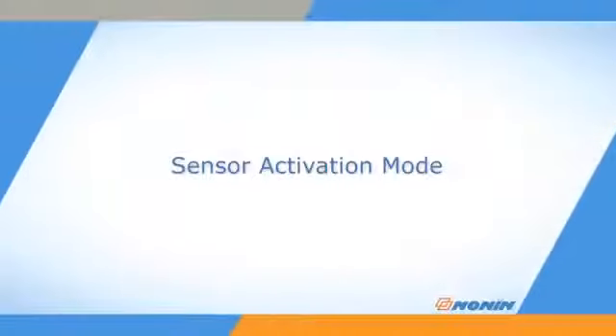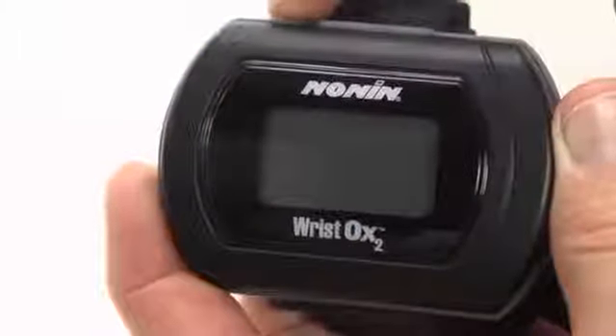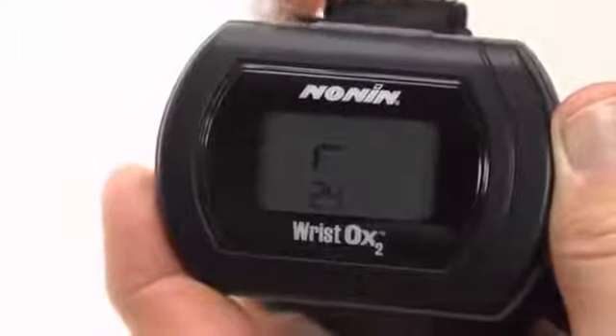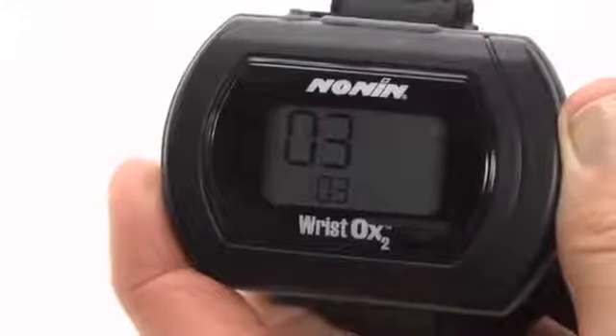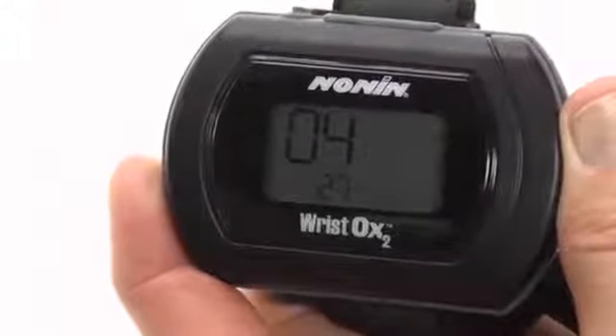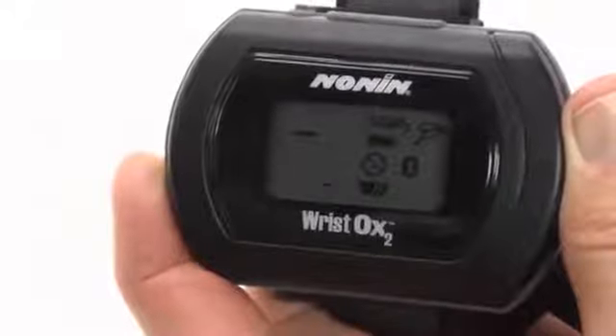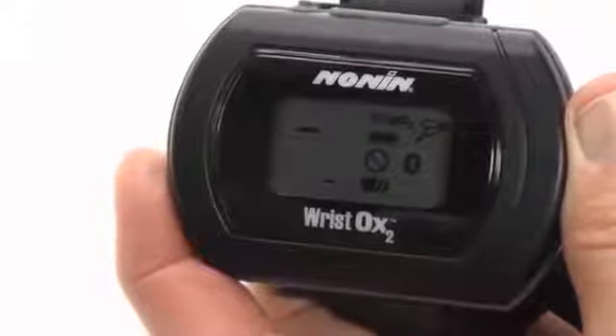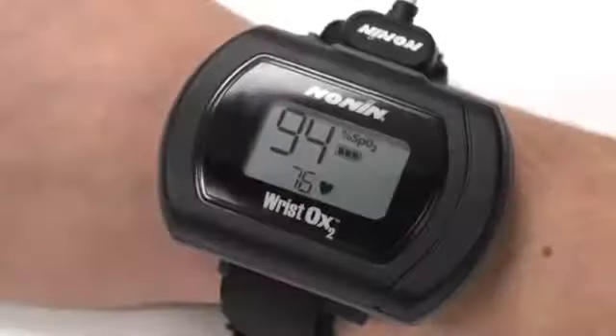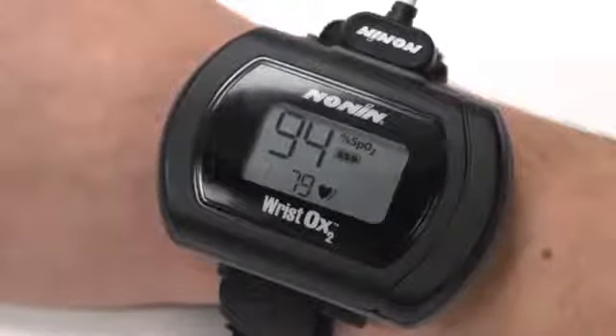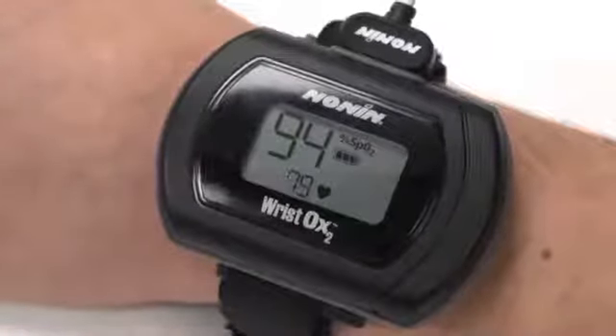Sensor activation mode can be programmed through the nVision software. The device turns on when the sensor is connected or when the activation switch is pressed. In this mode, the display can be set to show pulse and oxygen saturation levels or just the pulse and battery strength. This mode is useful when using a sensor that is not easy to remove from the patient, such as an adhesive disposable or wrap sensor.